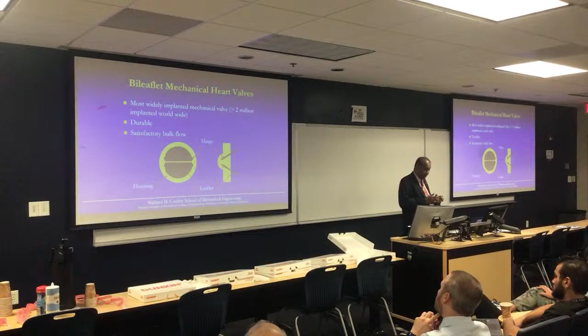Let's go down to the bileaflet mechanical heart valve. Like I said, today more than 3 million of these have been implanted worldwide. This is the most commonly used mechanical heart valve, and worldwide today, approximately 50% of valves are mechanical and 50% are biological. They're durable, and they have relatively good forward flow characteristics. But what I want you to do is focus on this area of the hinge where the leaflets open and close. These are three different designs of valves that have been used clinically. St. Jude Medical is the most commonly used mechanical bileaflet valve today, and has been around since 76, 77.